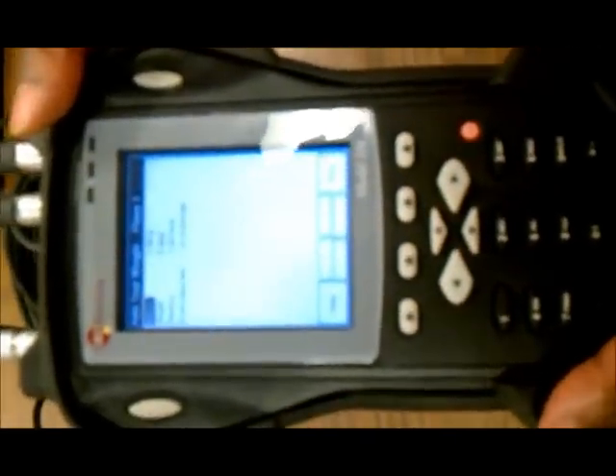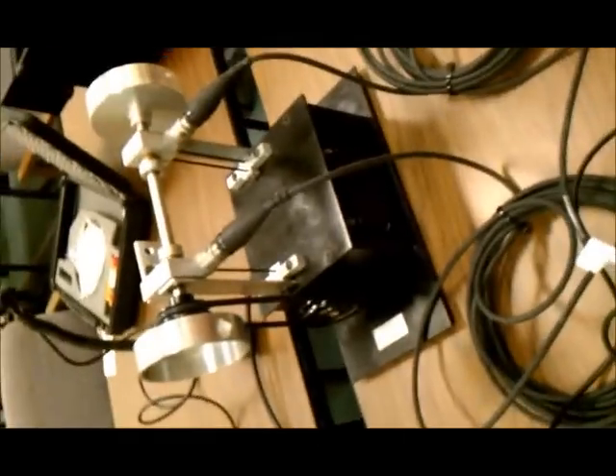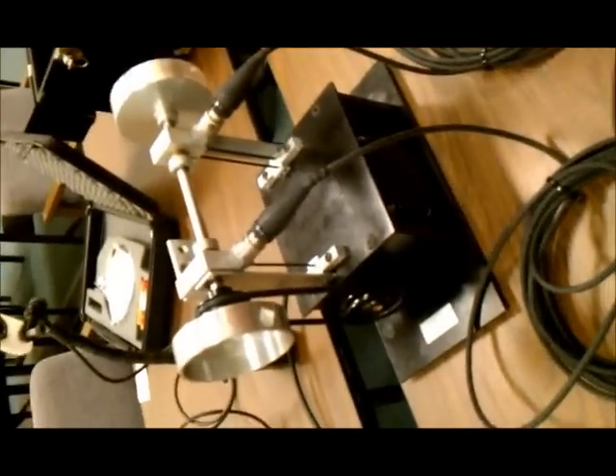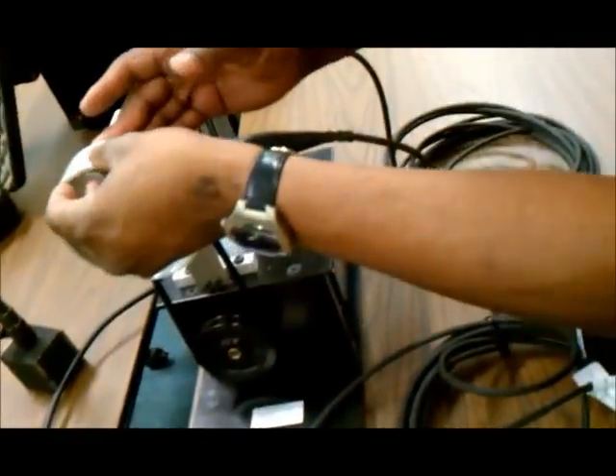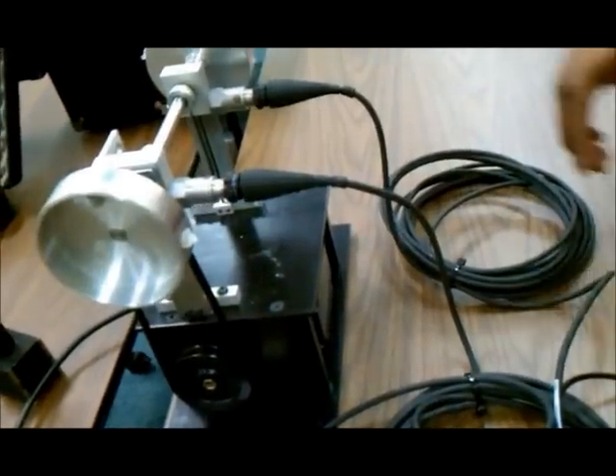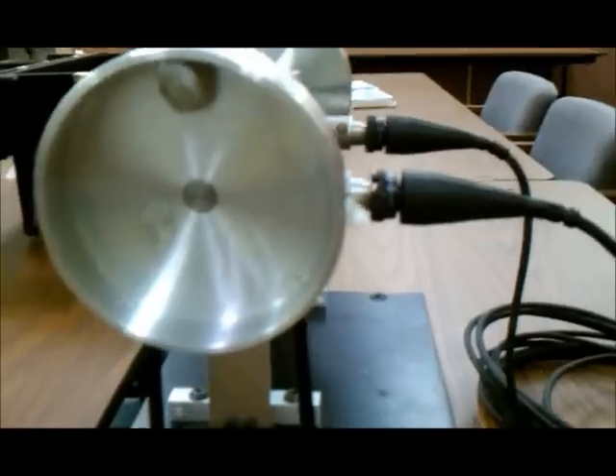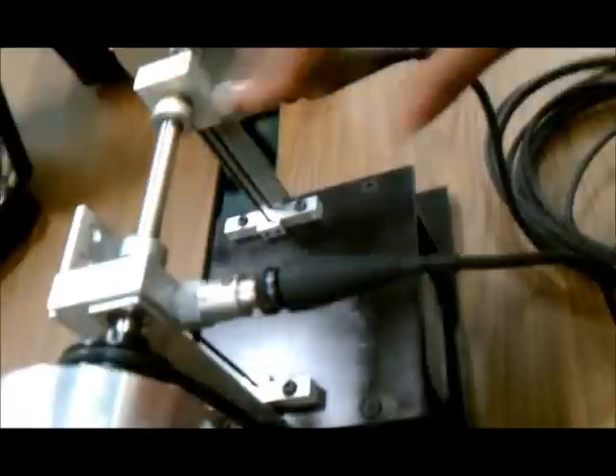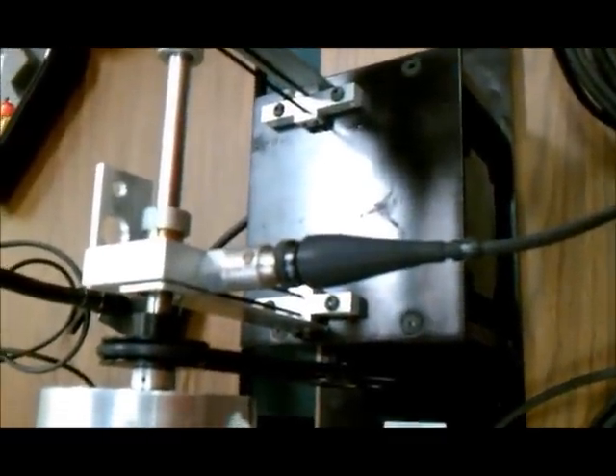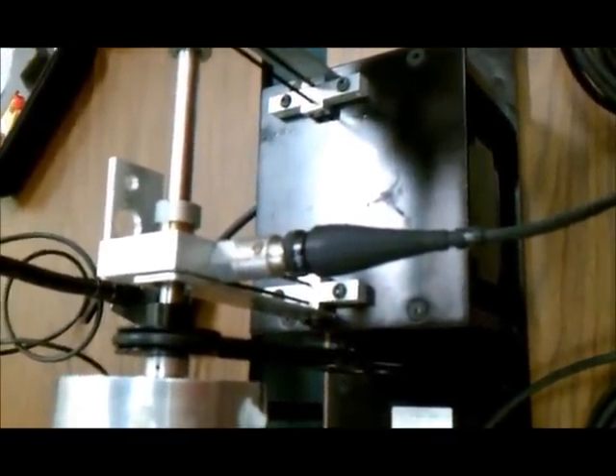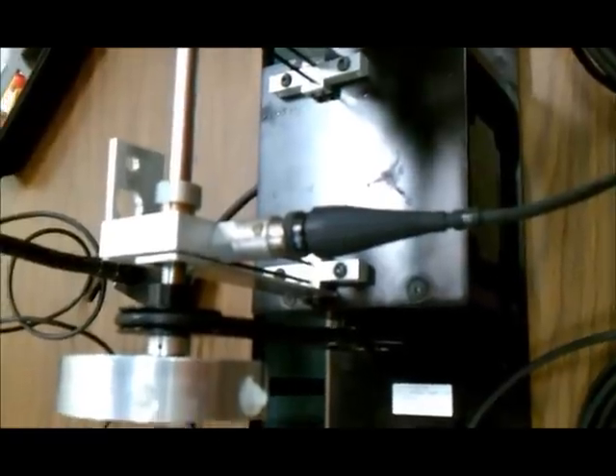And what it's going to ask us now is how much weight we're putting on it, what angle, and the radius that we're putting it at. For this, we're going to say we have 1 gram, and we are going to put it on our first plane, which is right here. So we'll stick that at our radius. And what we're using is the tape as our 0 degree marker. In actuality, since you're defining your angles, you can use anywhere, but you just have to make sure that you put it back to that angle for whatever you call it.